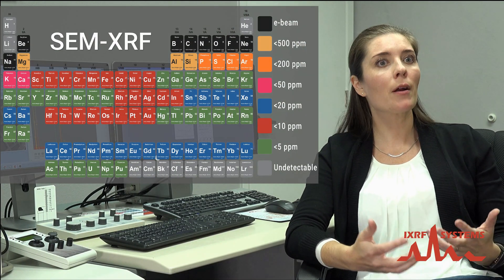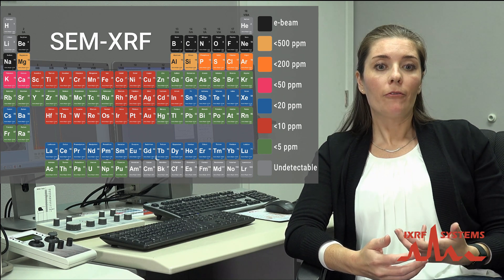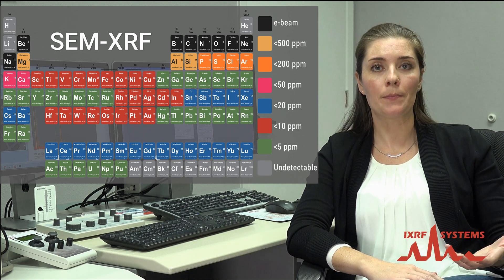I can certainly see some of the advantages from a qualitative perspective of what an XRF source can do when adding one to your SEM. But is this also true from a quantitative perspective? It's actually much better. If we have access to standards, we can really dive deep with quantitation using XRF. Earlier we talked about how with EDS we're limited for quantitation — we're at about a thousand parts per million. With XRF, again matrix and element dependent, we're able to get down into hundreds of ppm, maybe 10 ppm for your elements. So with proper standards, we can really dive deep on quant.